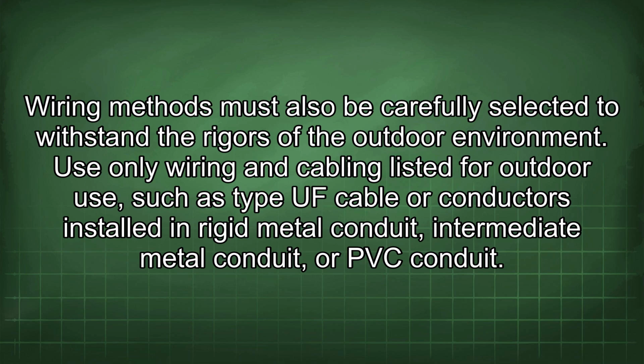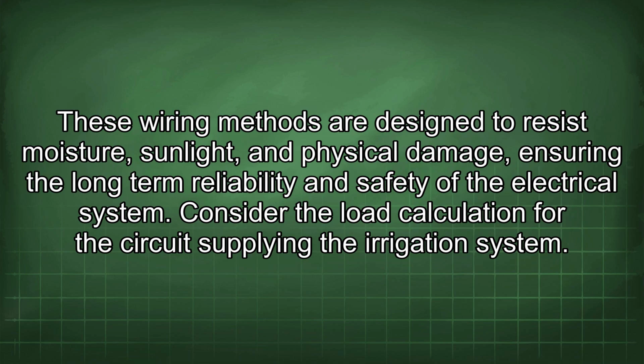Wiring methods must also be carefully selected to withstand the rigors of the outdoor environment. Use only wiring and cabling listed for outdoor use, such as Type UF cable or conductors installed in rigid metal conduit, intermediate metal conduit, or PVC conduit.